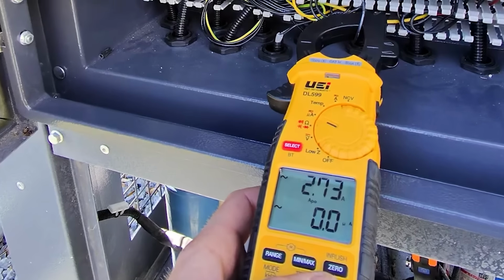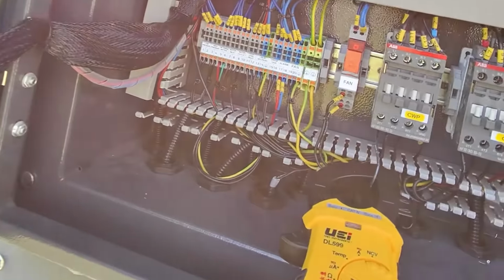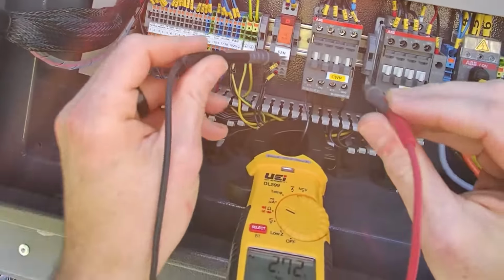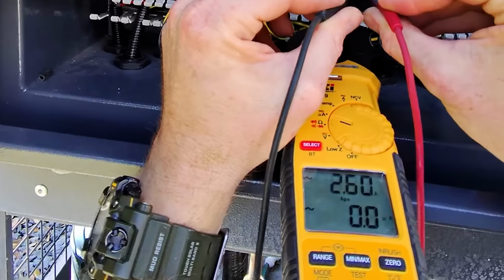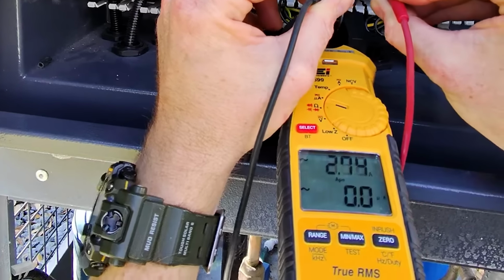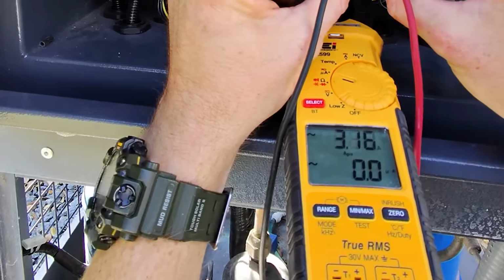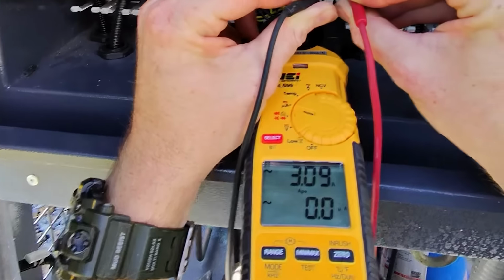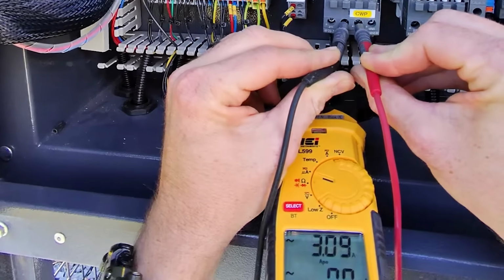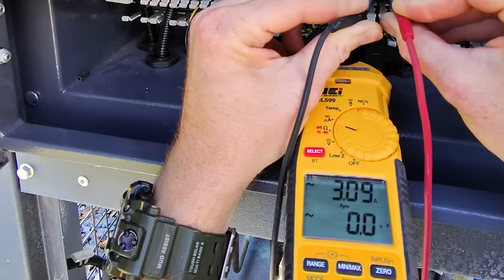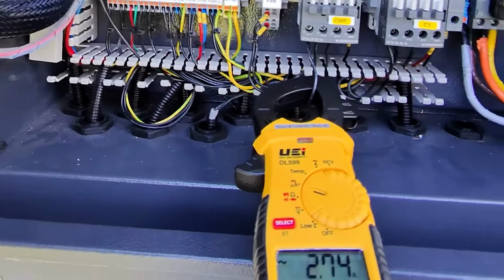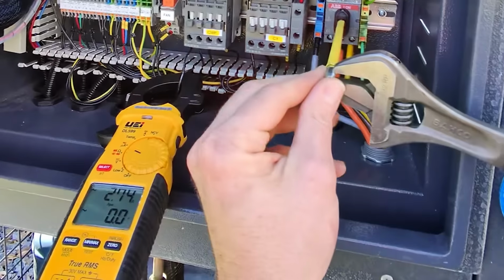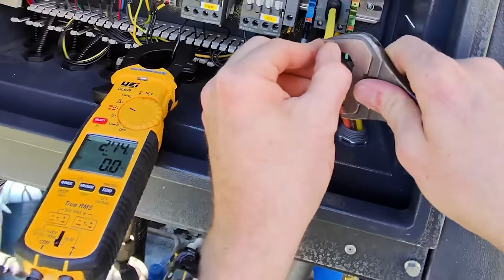We're still at 2.75. Our amps shoot up to 3.1 when the compressor turns on. And it's tripping. It's tripping only when the compressor comes on. Okay. Need a new unit.